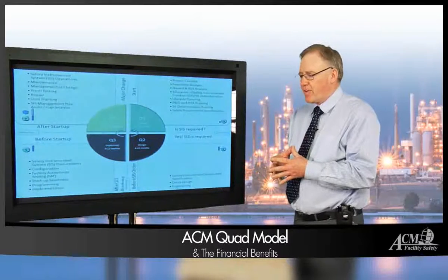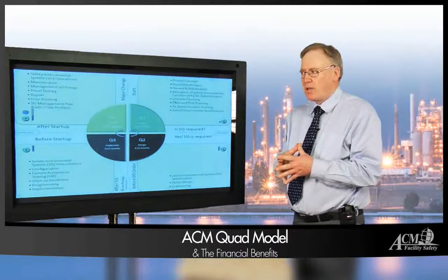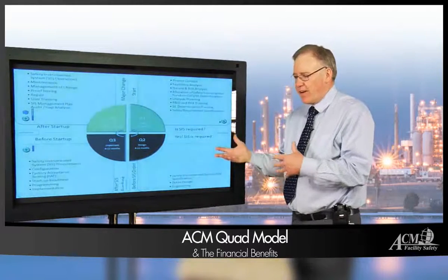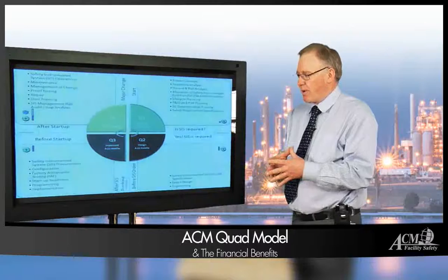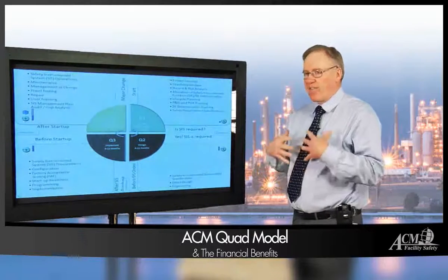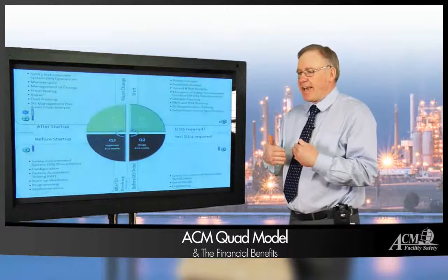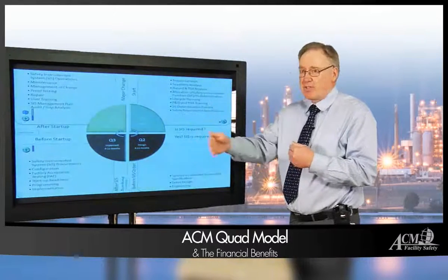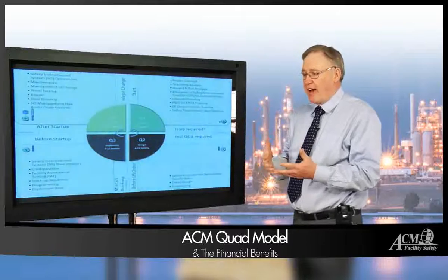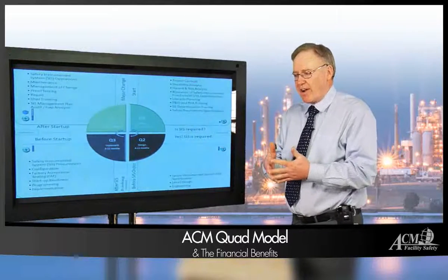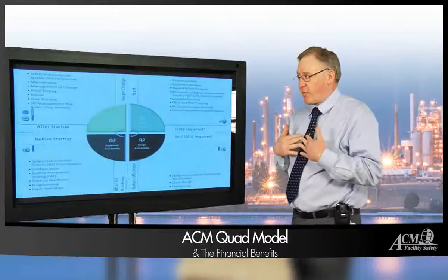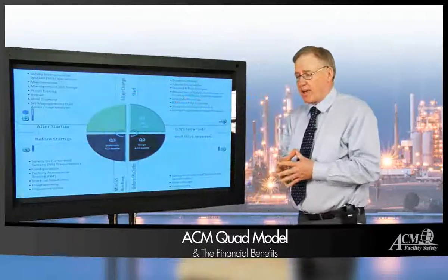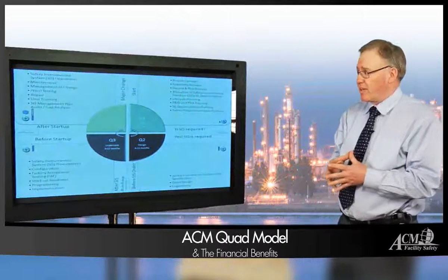But the other side of it is that if you have natural trips, for example, if you have a high level on an inlet separator and your plant trips successfully, well, you can take credit for that, so that you can delay testing your system for another 36 months or another 60 months. So in actual fact, you're monitoring the functions that are actually occurring, and you can take credit for that in the 4th quadrant. And again, the standards will allow you to do that because you've actually proven that the functionality is still intact.